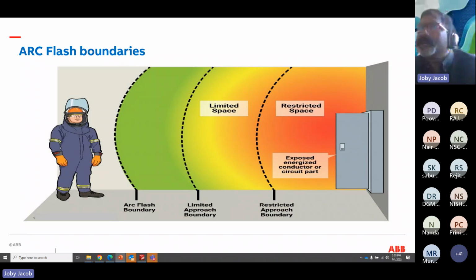Further to that, if you're too close, we call it prohibited approach space. Restricted approach space is further out from that. For example, if you're standing in front of a panel at the door, that's the restricted space. If you are inserting your hand inside the panel door, that's a prohibited approach space. Further out from that, you have the limited approach boundaries.